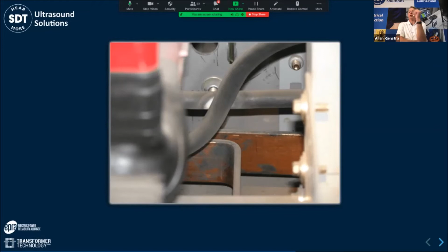Now here's something you'll see in industry a lot. This is a high voltage cable, and there's actually two high voltage cables. This is a classic case of poor workmanship or carelessness, where these two high voltage cables were installed and allowed to be in contact or too close proximity. Over time you get a bit of a bird caging effect, or insulation breakdown in the outer sheath of that cable, and you start to see that white buildup. Again, no heat, but lots and lots of corona discharge. This was something Craig was able to detect with his SDT 340.